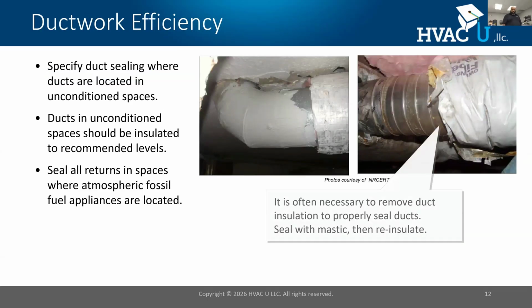What about ductwork efficiency? We mentioned that we want the ductwork to get our conditioned air from point A to point B. It needs to do it quickly. So there are a couple of things we need to look at. One, are the ducts sealed? Now, here's the thing. In order for ducts to be sealed, they should be properly sized. And we properly size our ducts by using industry standards like ACCA Manual D. When we do a Manual D and the ducts are sized appropriately, then we can seal the seams. When we look at the seams of ductwork, oftentimes in older construction homes, those seams were not sealed. Aeroseal did a study on this maybe some 20 years ago, and it's an average between 20 and 40% loss from your supply to the rest of your ductwork. So you're losing on average roughly 30% if your ducts are not sealed.